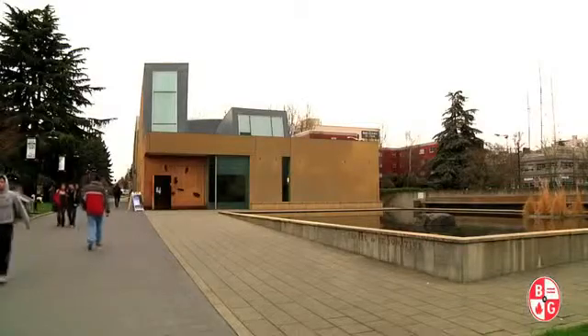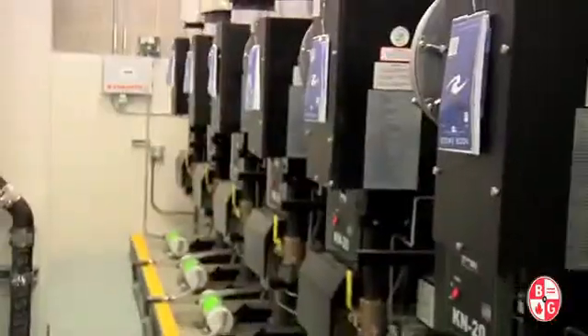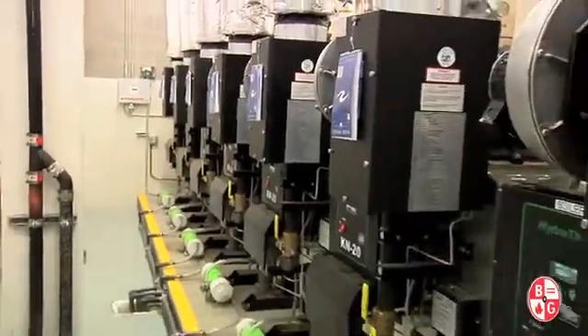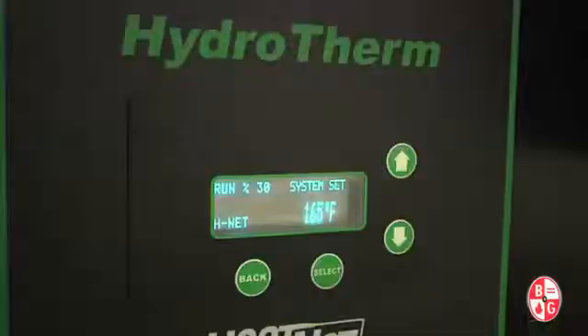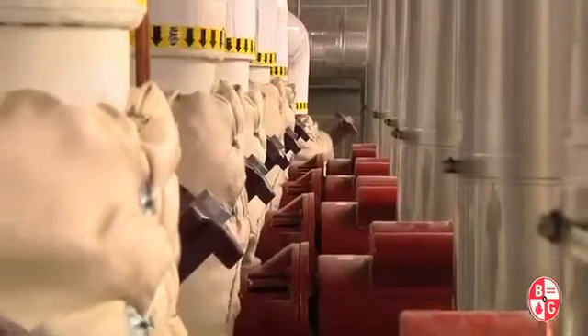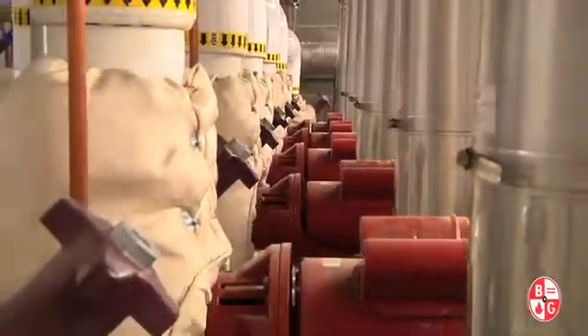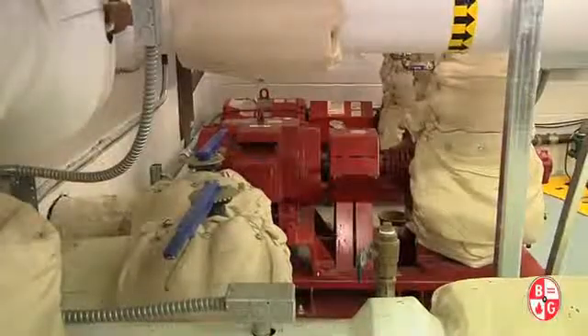Like many established institutions, Seattle University was on a legacy steam system first installed over 100 years ago. The university decided to go with a campus-wide hydronic system, starting with a unique retrofit to the university's boiler room. This first phase of the project utilizes a primary-secondary pumping arrangement to heat 5 buildings on campus. The new boilers, capable of producing a total of 14 million BTUs, are equipped with a number of B&G Series 60 pumps, while the buildings themselves are served by VSX pumps.